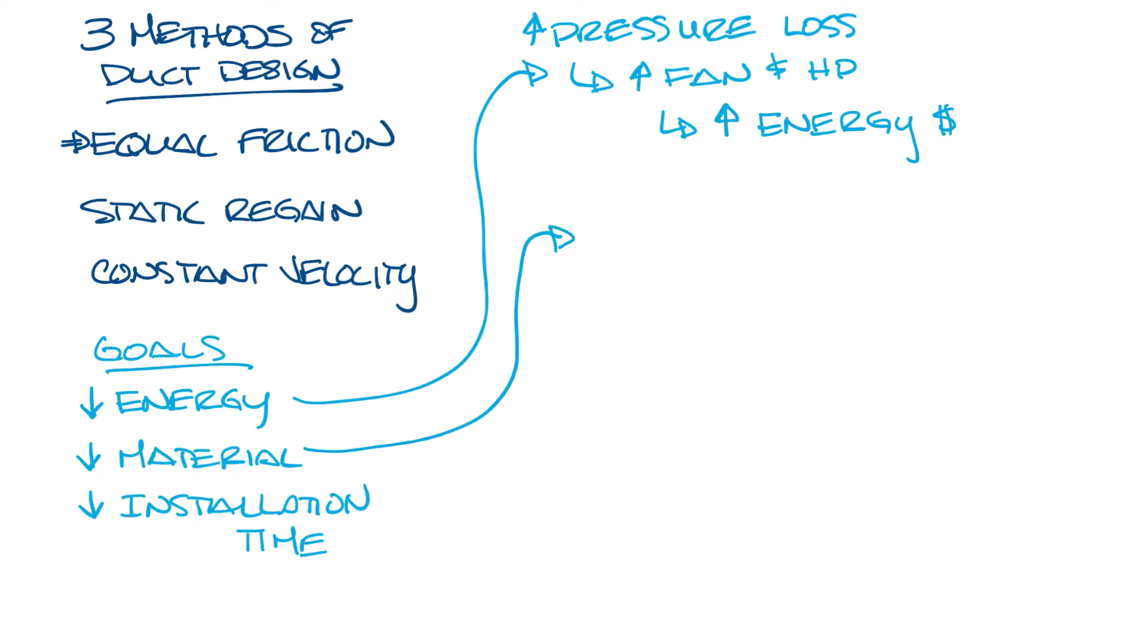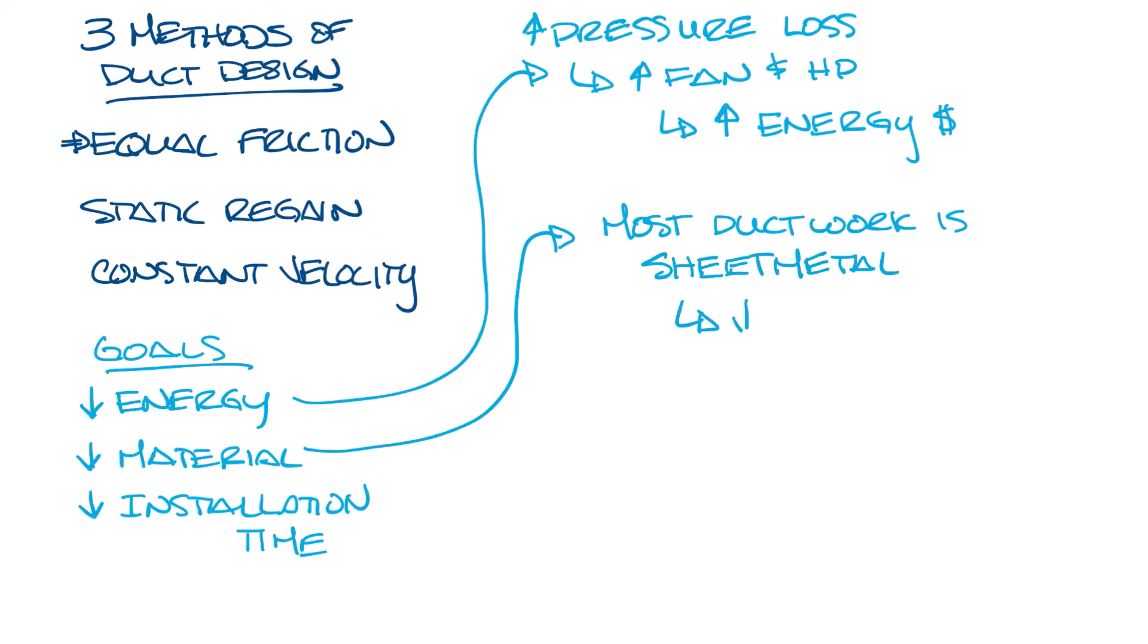From a material standpoint, most of a building's ductwork is sheet metal, only switching to flex duct to connect to the diffusers, so ideally you want to minimize your duct size to use as little sheet metal as possible. However, there is a trade-off between duct size and pressure loss that we'll talk about in a minute.